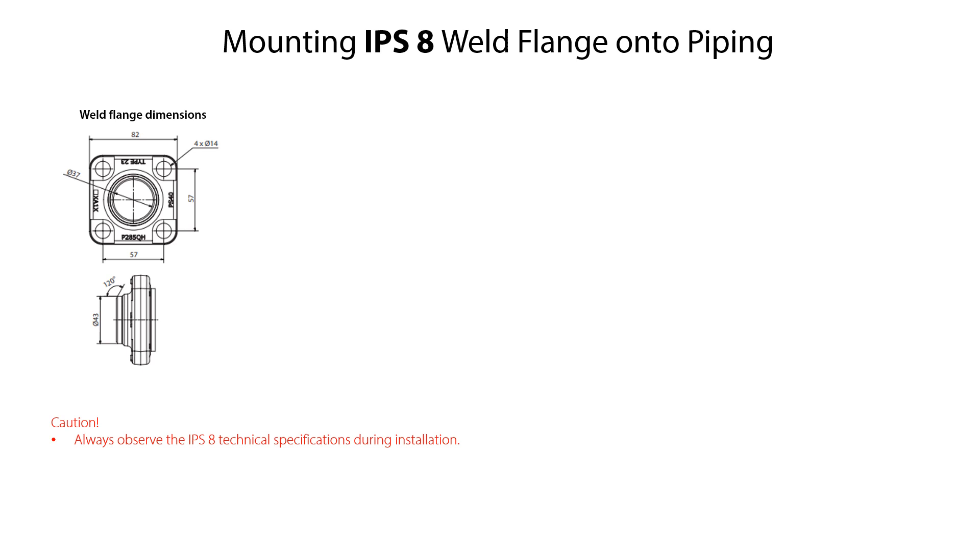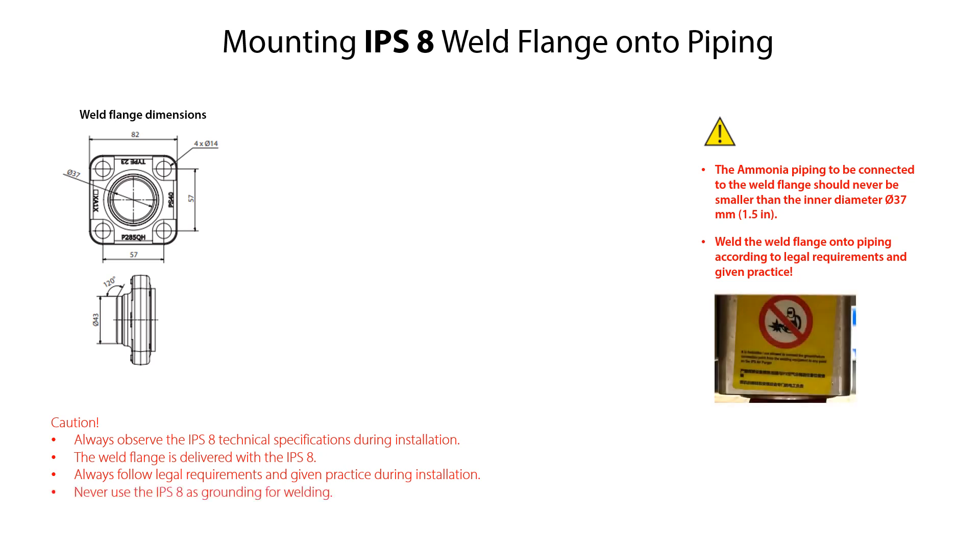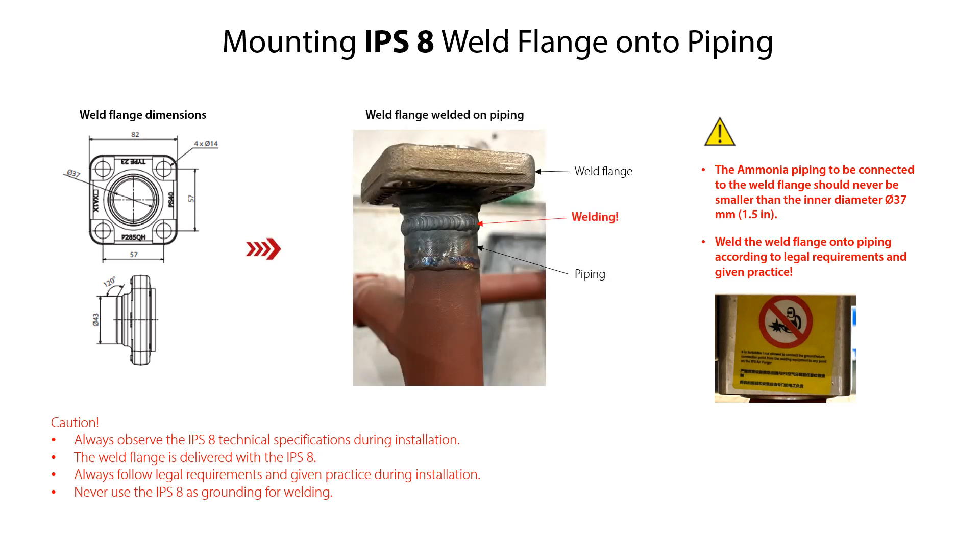Before we can locate and fix the IPS-8 on the support construction, we first need to ensure that the weld flange for connection between the IPS-8 and the ammonia plant piping is correctly welded onto the piping. This weld flange is delivered together with the IPS-8. The ammonia plant piping to be connected to the IPS-8 weld flange should never be smaller than the inner diameter of 37 mm or 1.5 inch of the weld flange. It is very important that the weld flange is welded onto the piping according to legal requirements and given practice. It is also very important that the IPS-8 is never used as grounding for any welding, as specified on the warning label mounted on the weld flange. Here you see an example of how the weld flange is welded onto the piping.